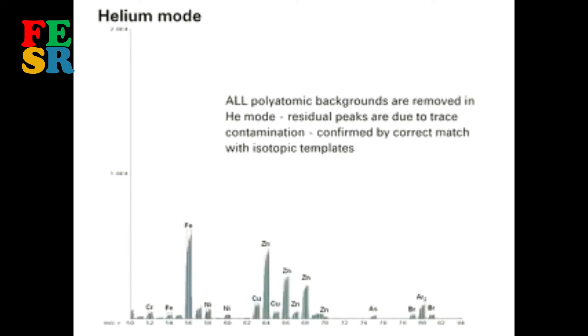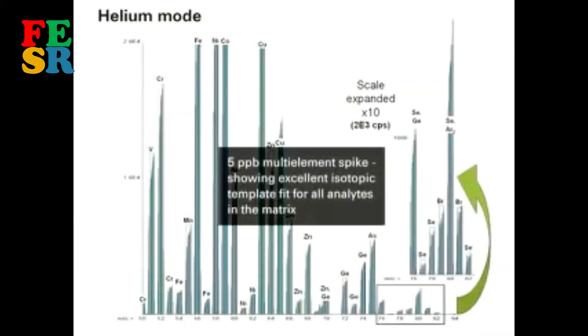Helium mode has removed all polyatomic interferences simultaneously. Finally, adding a five-parts-per-billion multi-element spike confirms all analytes are easily measured in this very complex sample matrix.